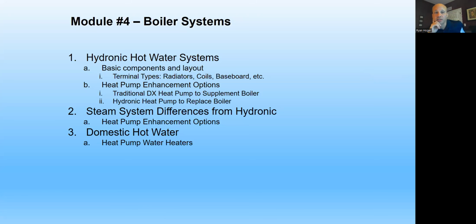And we'll go through hydronic boiler systems, hot water systems, a little bit of steam also, but mainly hot water hydronic systems. And we'll talk about how we can make those into heat pumps. Either heat pumps themselves for the boiler, make a heat pump boiler, or supplement the boiler with a heat pump. We'll talk about both kinds of scenarios. But first, we'll go through how a basic hydronic system works so you know what the hell you got when you see one of these out there. More questions? Anybody?